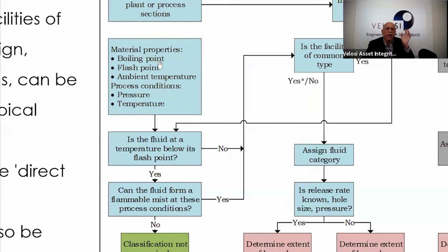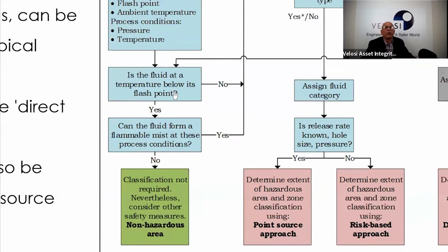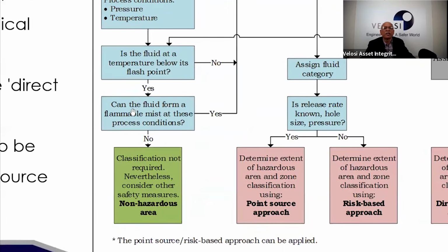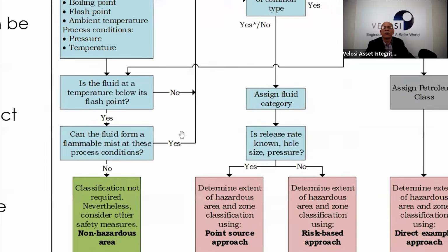Material properties of all the fluids contained by each equipment in that particular area. What is the boiling point? What is the flash point? Ambient temperature, and process conditions like pressure and temperature. And then, is the fluid at a temperature below its flash point? Can the fluid form a flammable mist at these process conditions? And so on. If the answer is no, then classification is not required. If yes, then we go back to this side.